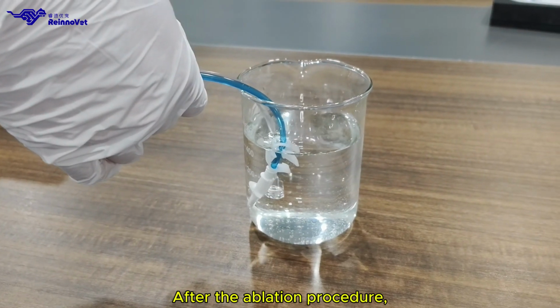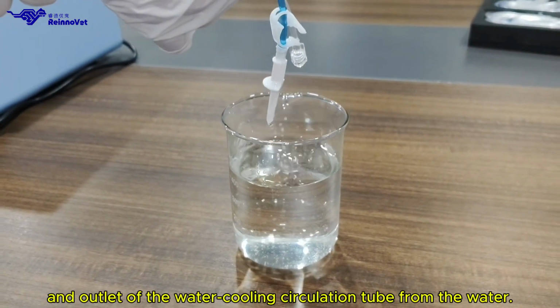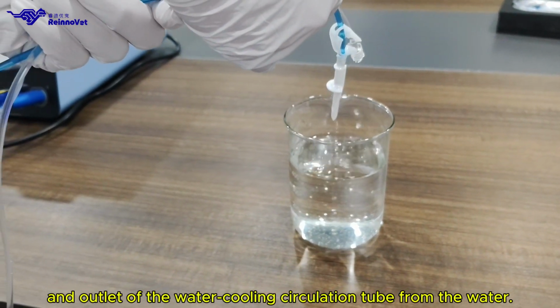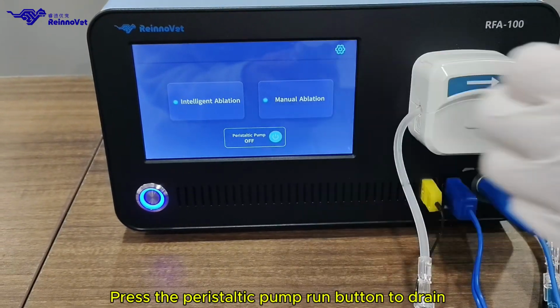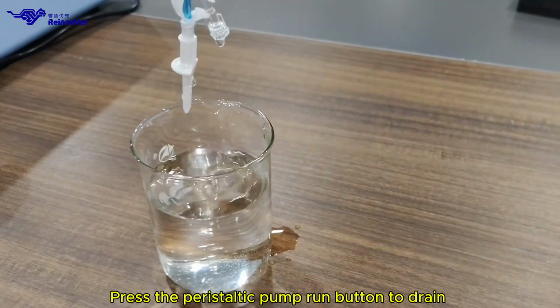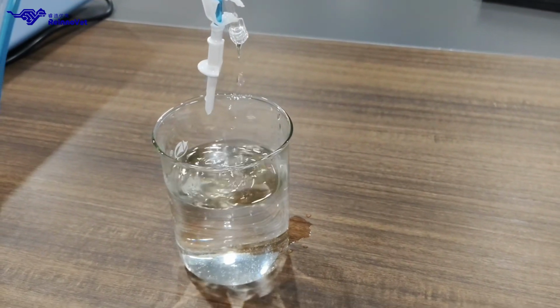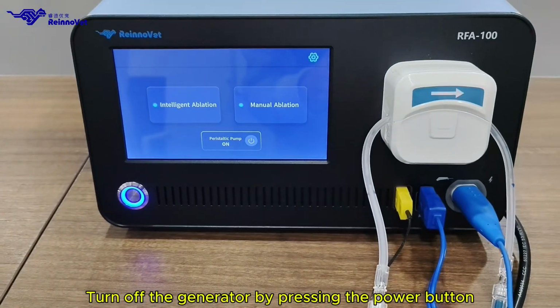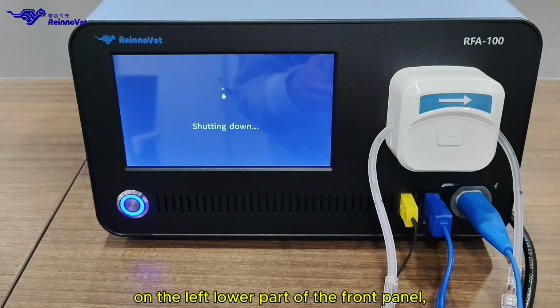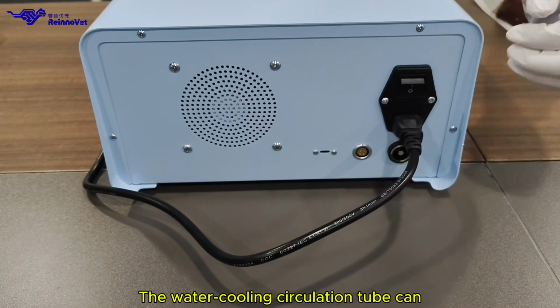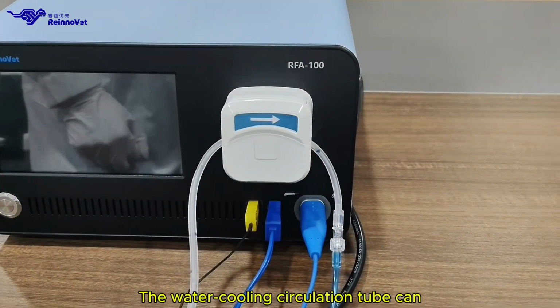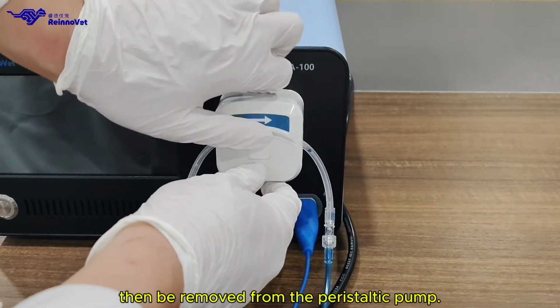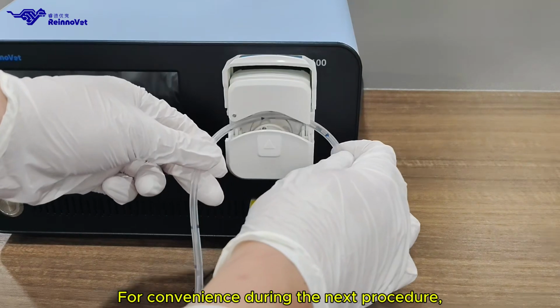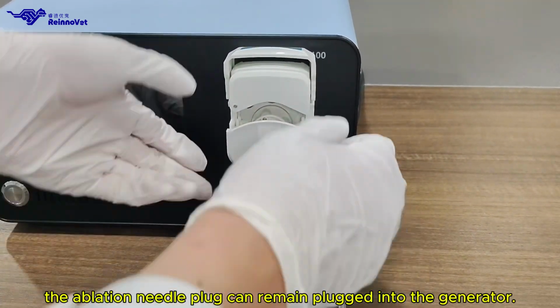After the ablation procedure, remove both the inlet and outlet of the water cooling circulation tube from the water. Press the peristaltic pump run button to drain the cooling water from the tube. Turn off the generator by pressing the power button on the left lower part of the front panel, and then press the boat-shaped switch on the back to power off. The water cooling circulation tube can then be removed from the peristaltic pump. For convenience during the next procedure, the ablation needle plug can remain plugged into the generator.